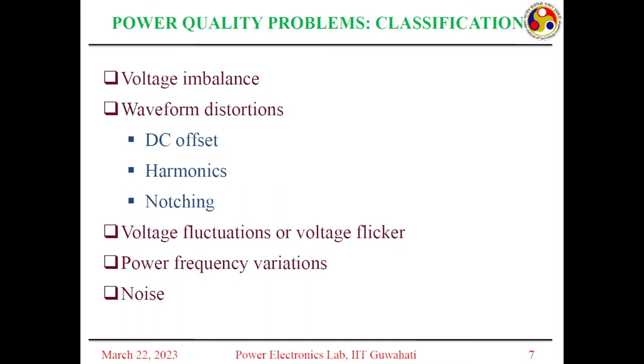So we will see what the sources of these power quality issues are. Why are you having these power quality issues? Basically, we have 3 different sources. We can classify them: one is the utility side, another is internal sources, and then power electronics related operators. Utility side issues are like lightning strikes, power factor correction equipment, faults, and the switching of other equipment. For example, if there is a lightning strike at the source side, there will be an impact on the bus voltages at the customer side. So this is categorized as a utility problem. Although it is a natural problem, we categorize it as a utility problem.